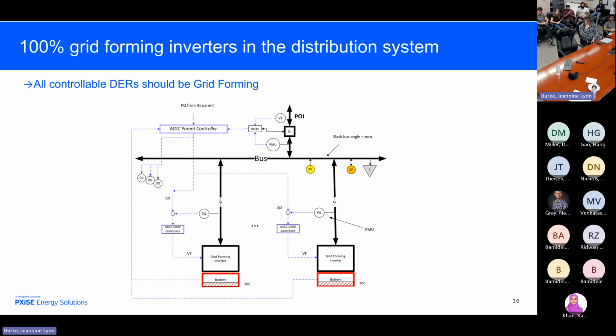The customers call up, hey, my clock on my refrigerator is 2 minutes off. What gives? So we can solve the time problem by controlling, if this is a pure island, this bus angle to 0 using the PMU. We just set the bus set point angle to 0. Now we have state variable control. So now we control the voltage and the angle at this point, and guess what? The clock stays at GPS time.